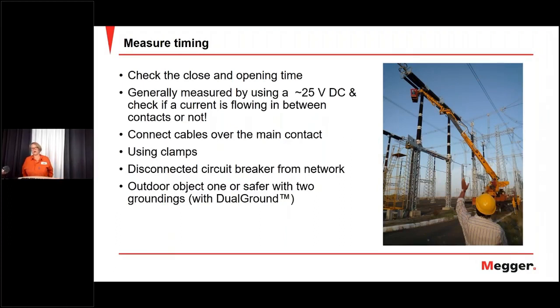Measuring timing. Yeah, now we're outside, and of course, it's a different situation. And they really recommend to work with two sides grounded, with dual ground. It is connections directly at the phases. And yes, you do ground on both sides, before you do any connections. But of course, the cables are connected up to this part, disconnected parts, but influenced by nearby lines and bays and overhead lines. So it's really wise to work with two sides grounded here.